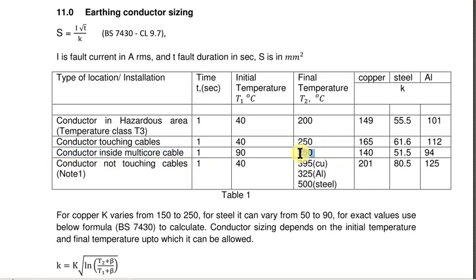When a conductor is not touching any cable, the final temperature can be a higher value. It can be 395 for copper and 500 for steel. But this case is very rare because very rarely you will find a conductor which is not touching any insulation. So better go for the first two cases.